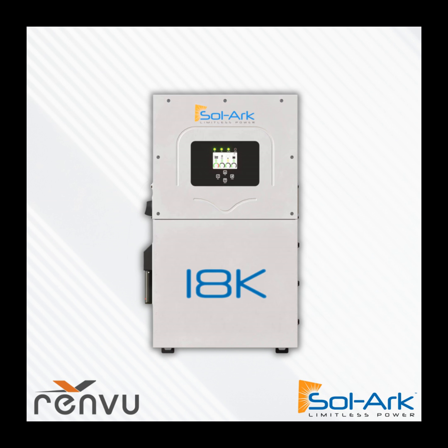You don't overload. What I'm trying to say is, don't use the grid pass-through capability on every commercial project. Only use it for the whole building backup projects where you can price accordingly. If you're just throwing out backup power as a value add without really pricing in the need for it, I would say don't not sell backup power. Don't do economic-only, no-backup projects, but consider load side interconnections and essential backup rather than whole building backup for commercial. They're just as economic. In fact, they can be more economic because, just like a load side connection for residential, it's a little bit faster of a process than doing the full service backup.